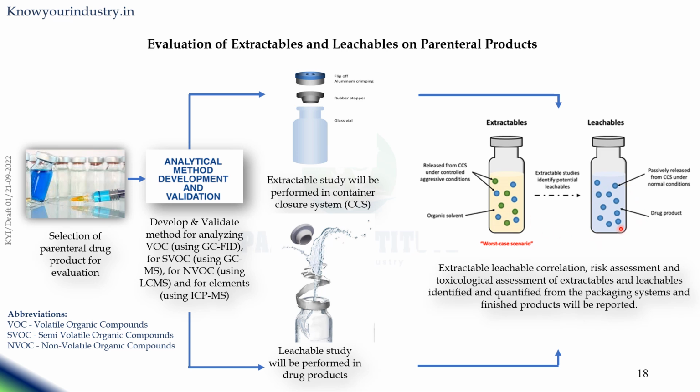And in case you find a leachable above the safety concern threshold, you have to do the risk assessment, a toxicological assessment for the particular leachable. Whether it is safe or not, you have to establish. And in case it is required to monitor the level of leachables in the products, you have to perform it as part of the release of the product.